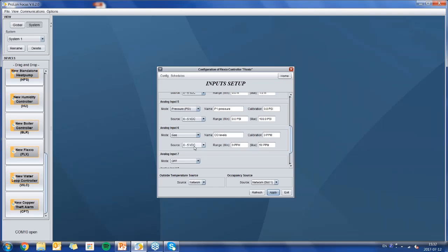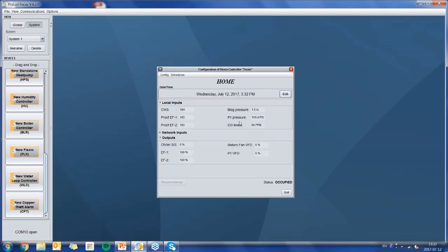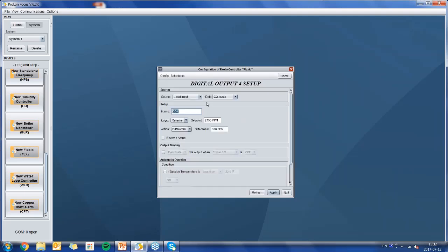Here we might have an actual 4 to 20 milliamp signal going in. So there we go, here I've got my CO levels. And if I go to, let's say, I just want to enable a contact which is going to start a fan, open up a damper, and so on. So I could go into my DO4, my local input will be the CO levels, and I'll call this CO evac, for evacuation.